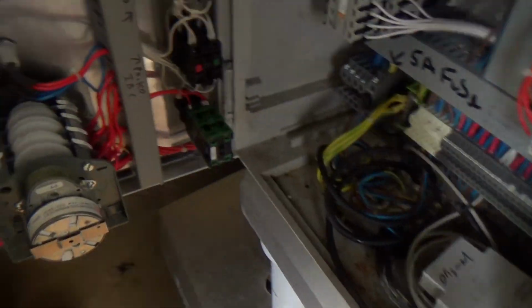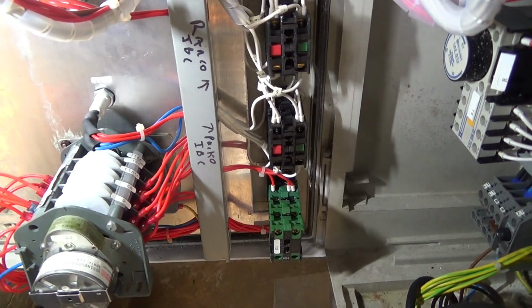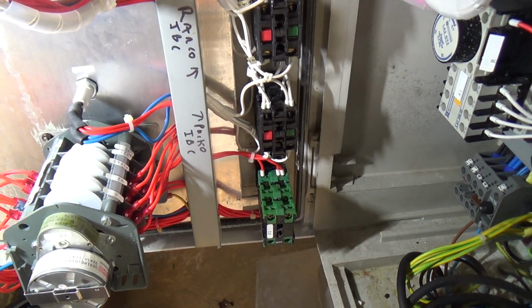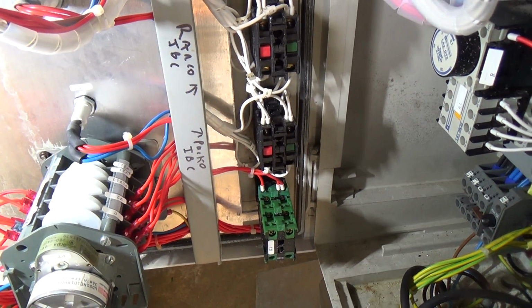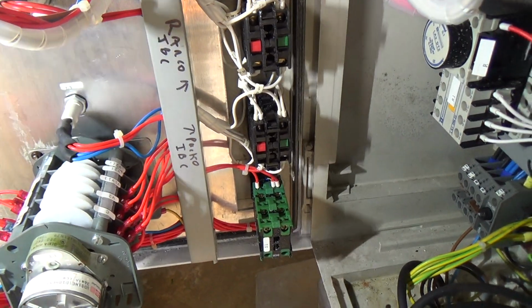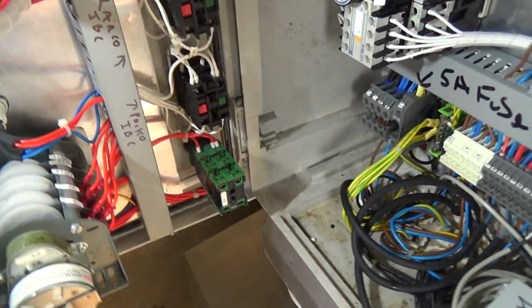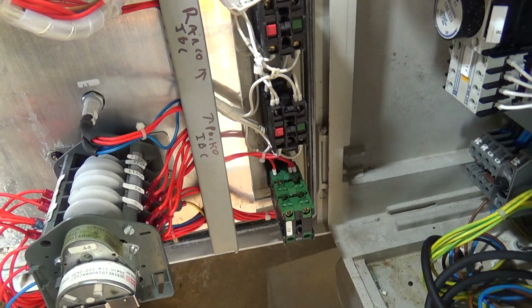So you can gain a little bit by not making too much, you just make enough. So we've had problems in the past where these switches that go between plus and minus 50% play up, because they're switching low voltage and they're really mains rated switches, so the contacts get a bit of corrosion on them or something, and then a little bit of resistance mimics having ice on the sensor. So I think we've confirmed the switches are okay.